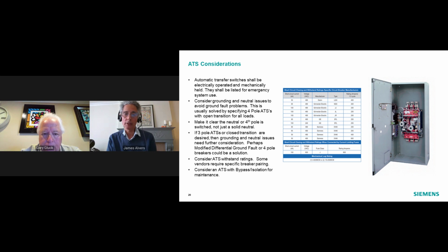where they have a specific rating that is not tied to a specific breaker, and you can use any breaker that has the right AIC and amperage. Sometimes that's better. Sometimes using the chart is better. It really just depends on the application and selectivity, selective coordination. You need to also consider bypass isolation for maintenance. So there's a picture of an ATS there. Under that ATS, if you had bypass isolation, you'd have more hardware so that you can bypass that ATS and actually service it, while still keeping your system running.